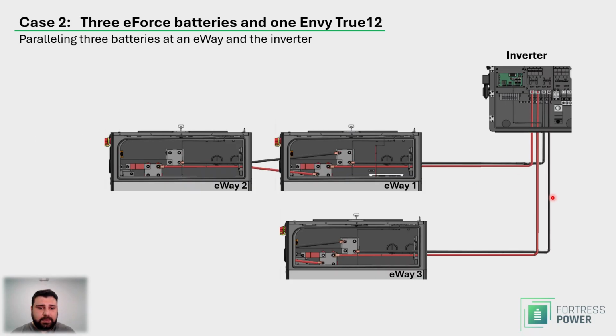So here's what we're going to do. Just like before, we have eWay 1 and eWay 2, but we remember that we had the second positive and second negative vacant inside the inverter. So just like before, we have eWay 1 and eWay 2 joining each other on the bus bars of eWay 1, and then that connecting to the inverter, thus paralleling the inverter, eWay 1 and eWay 2. But because we have the second positive and second negative port, we're going to connect eWay 3 to the inverter.